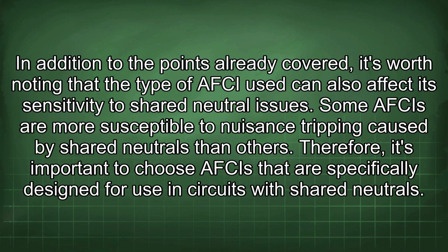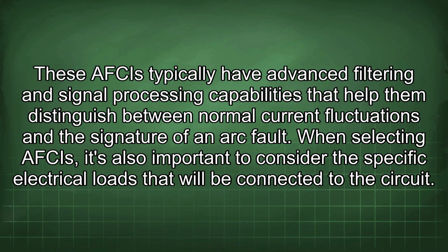In addition to the points already covered, it's worth noting that the type of AFCI used can also affect its sensitivity to shared neutral issues. Some AFCIs are more susceptible to nuisance tripping caused by shared neutrals than others. Therefore, it's important to choose AFCIs that are specifically designed for use in circuits with shared neutrals. These AFCIs typically have advanced filtering and signal processing capabilities that help them distinguish between normal current fluctuations and the signature of an arc fault.